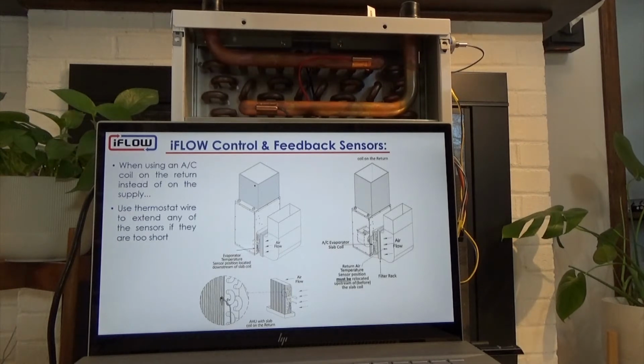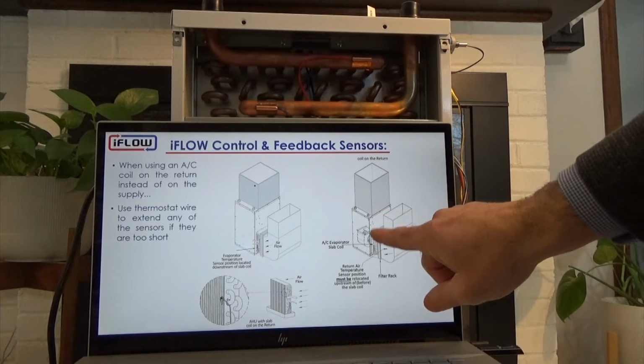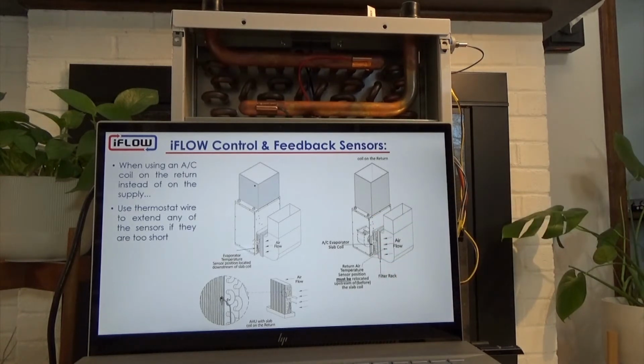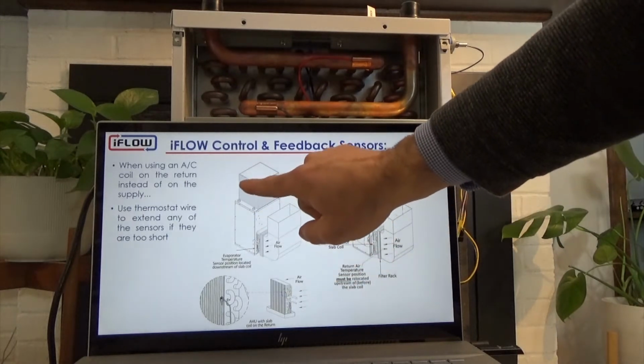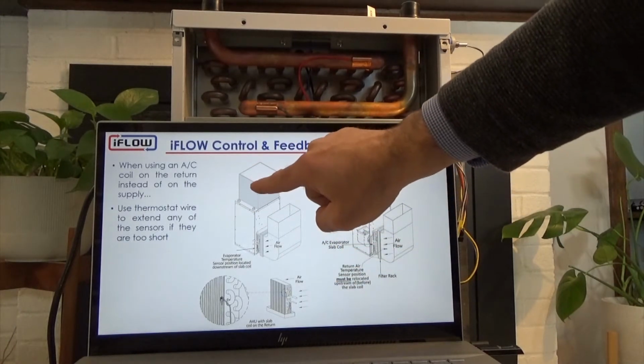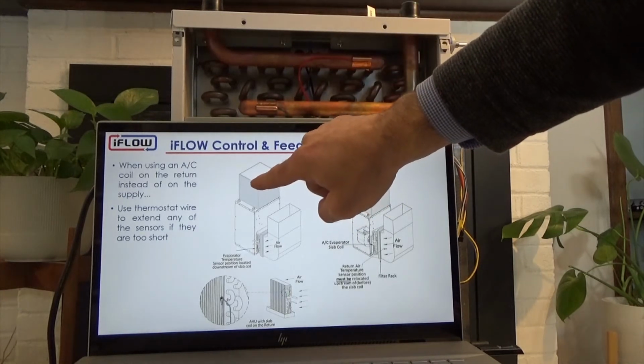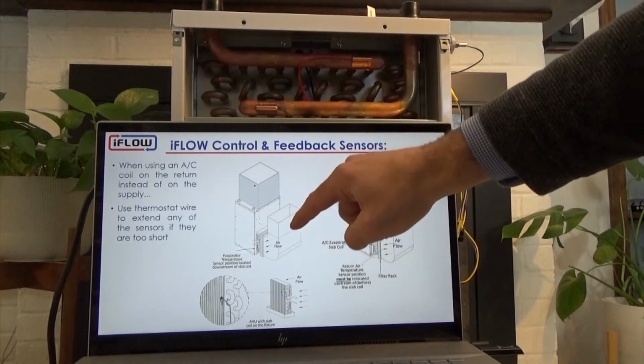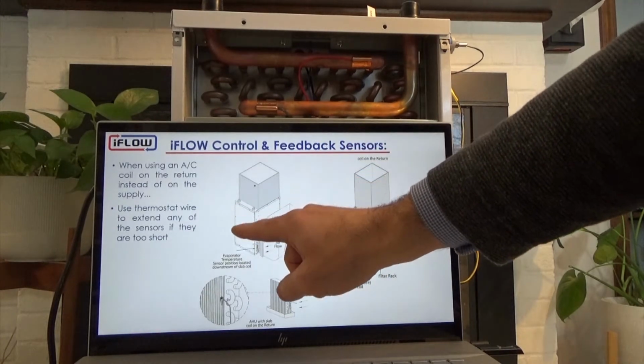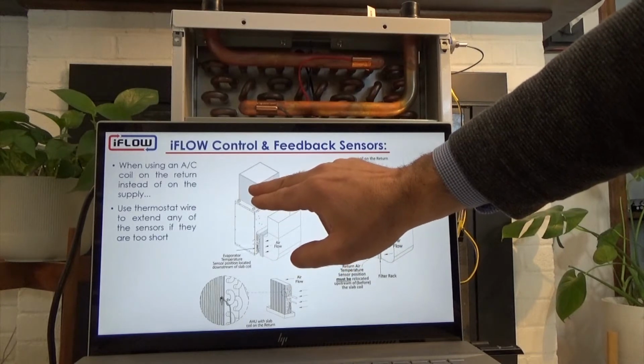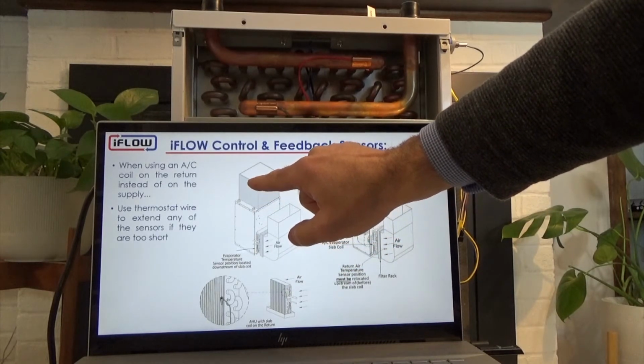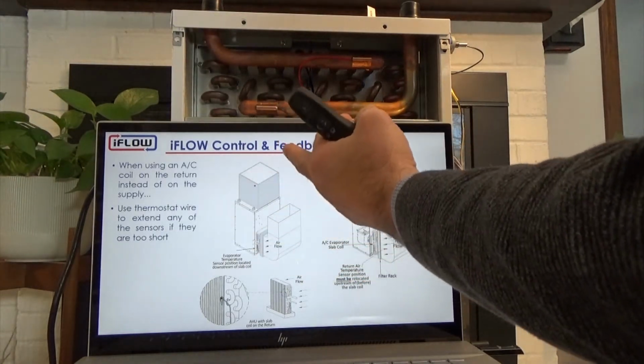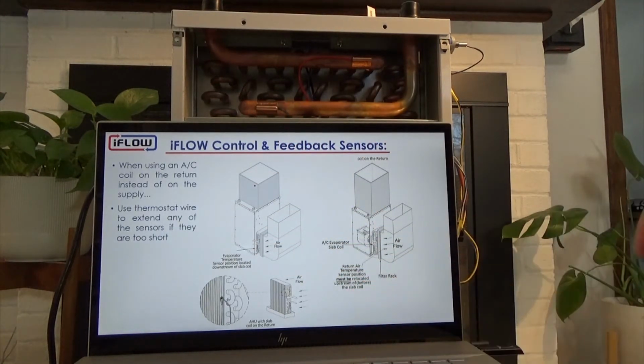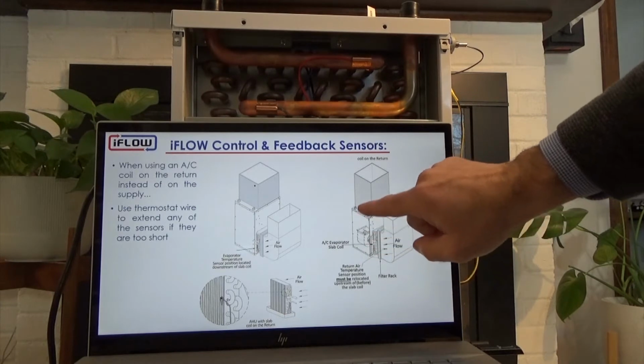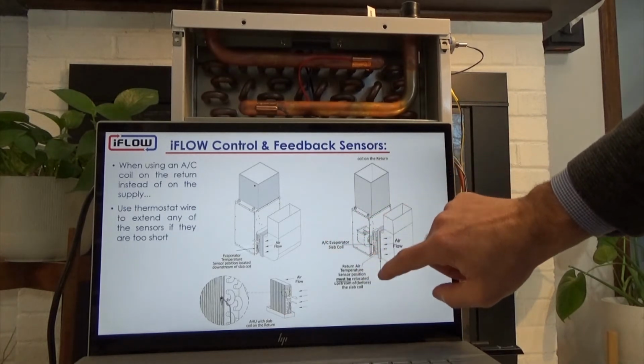So as I said earlier, when we do that, there are two things. If we're using a slab coil on the return, well, let's go to the regular system first. If we use an A coil on top, then we'll use our evaporator temperature sensor, strap it to the top without problem. So the return air sensor is seeing the proper return air, and the sensor is located properly on the top of the AC coil, and it's all good. When we use it on the return, then we have to relocate the sensor. The slab evaporator coil is going to be here.